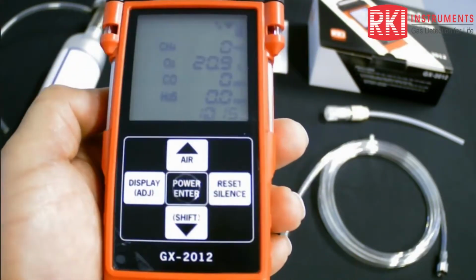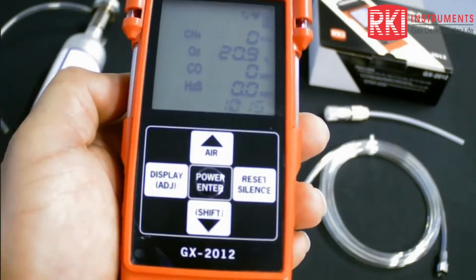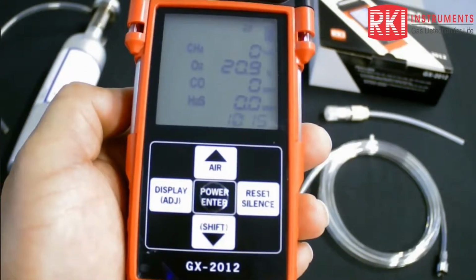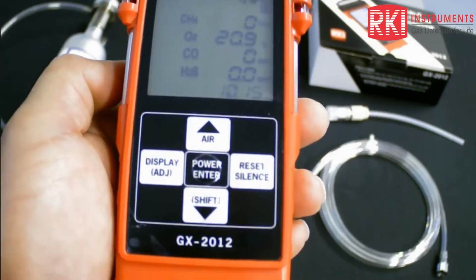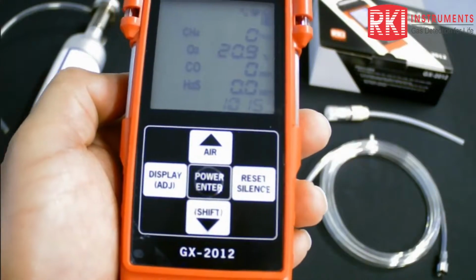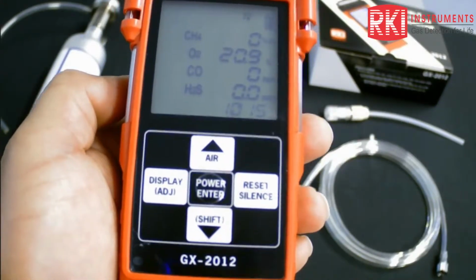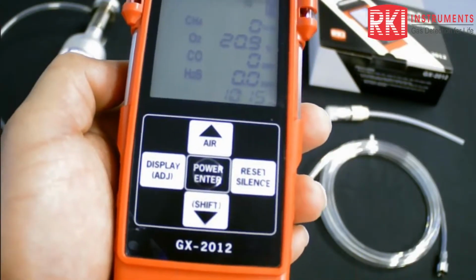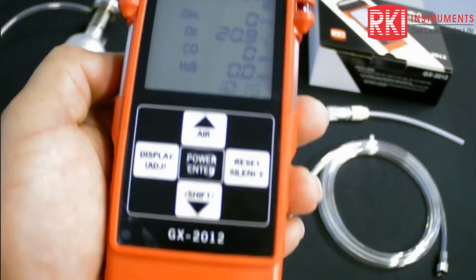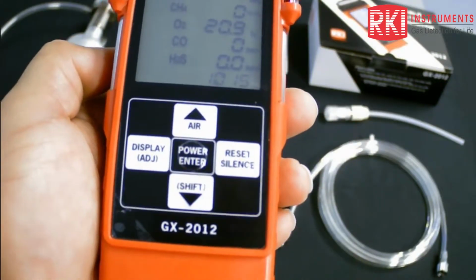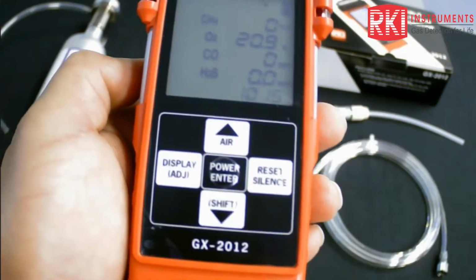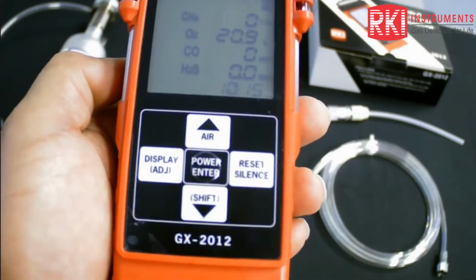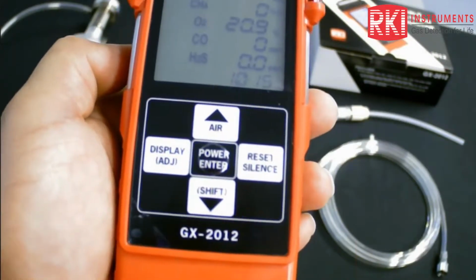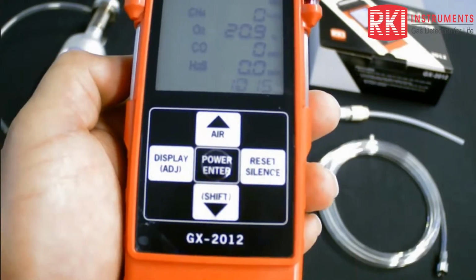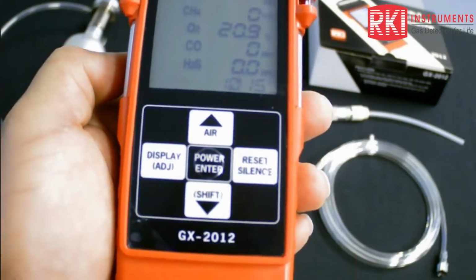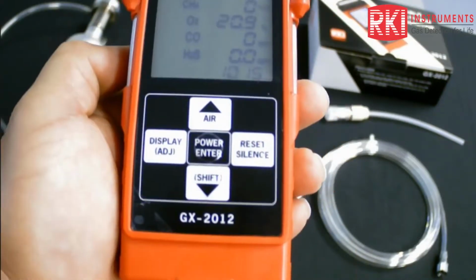which we call a thermal conductivity sensor. That sensor is similar to the LEL. It does have a couple of elements as well, a reference and an active. But in this case, there's no catalytic coating on that active element. Basically, we have the reference isolated from the active so that when the gas comes in through the unit and to the sensors, it actually cools down that active element in comparison to the reference element. So we apply a voltage and current to these sensors, whether it's the catalytic or the thermal conductivity. We heat them up to a certain temperature. In the case of the catalytic, the active element is heating up compared to the reference element. And for the thermal conductivity, the active element is cooling down compared to the reference. That's how we measure it.